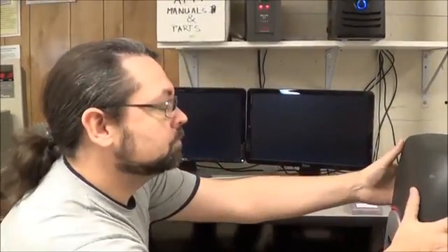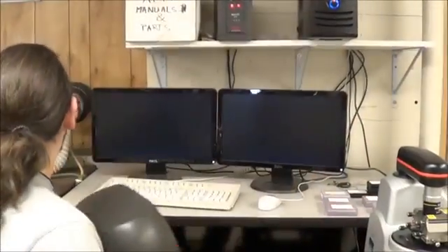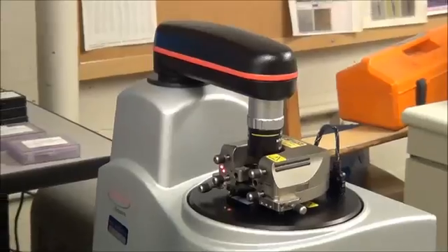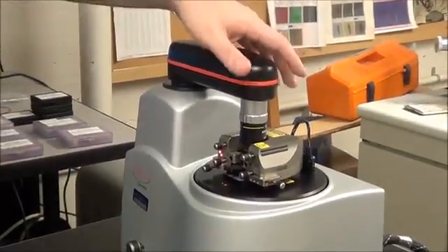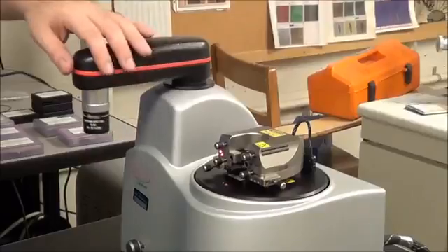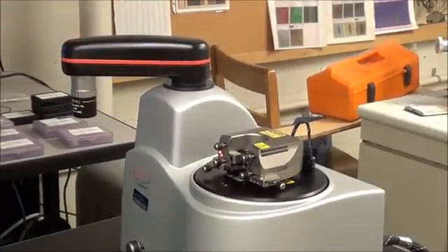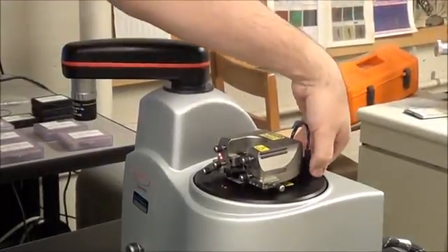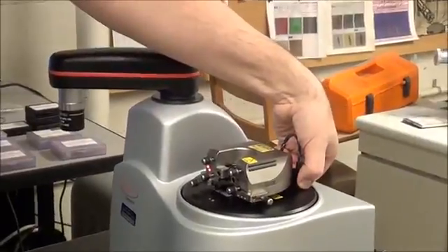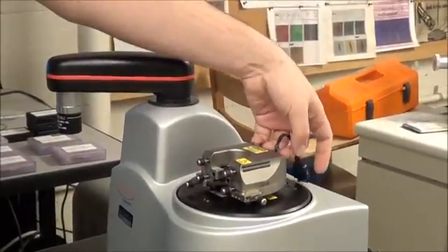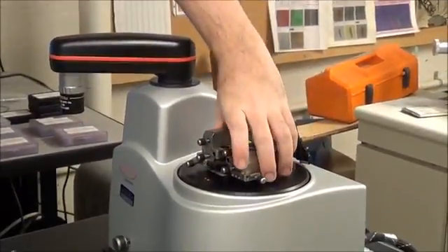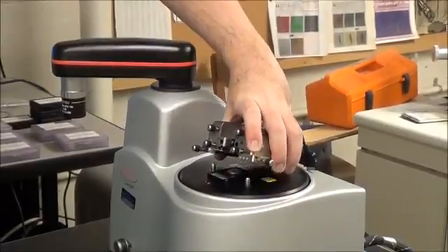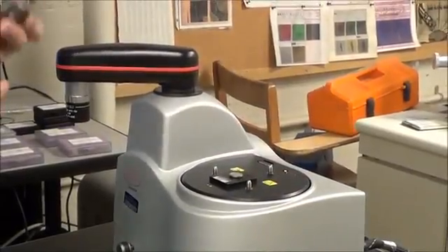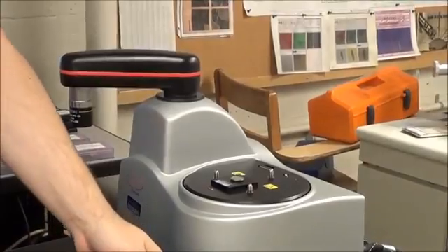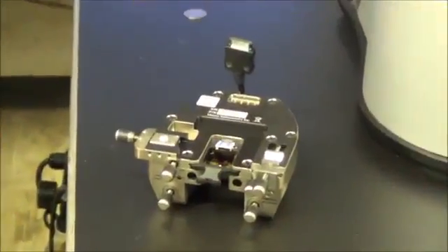While our software boots up, we remove the protective cover of the AFM. Swivel the microscope out of the way to gain access to the stage. To remove the stage mount, you must first unplug it. This is accomplished by squeezing both sides at once and then gently pulling it free. Then, to remove the probe mount, lift it by first tilting it towards the back of the stage, then lifting it clear. The probe mount should be placed upside down on the table.